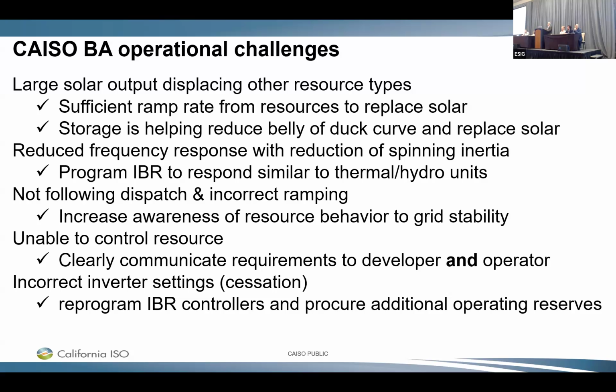What we found was a lot of the operators of these plants really had no idea what they were doing, and many of them did not even have control of the plant. They'd be located remotely. We would call them when we had a transmission overload and try to decrement them or reduce the output, and they would not respond. We'd call and they'd say, well, I can't control my plant. So we've actually had transmission operators de-energize the line to the plant just to get that reduction in output, but we have been able to work on that as well.